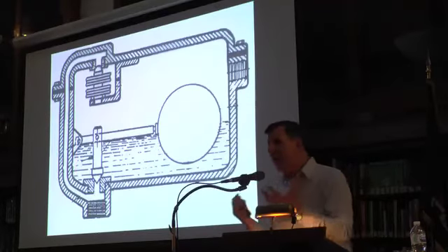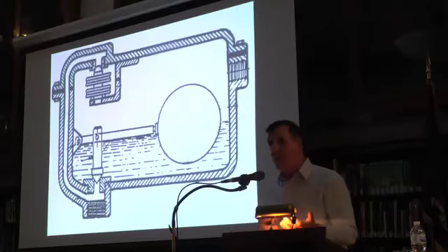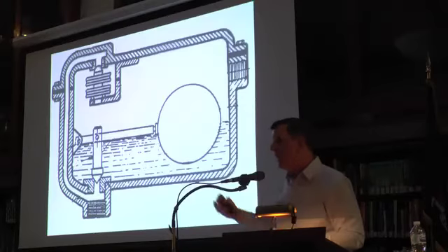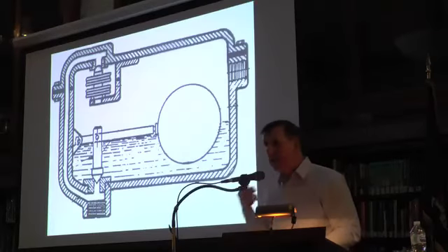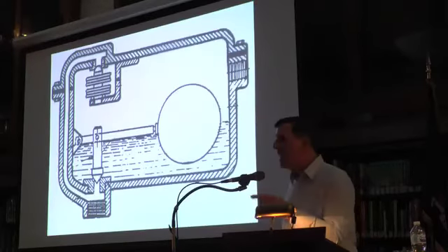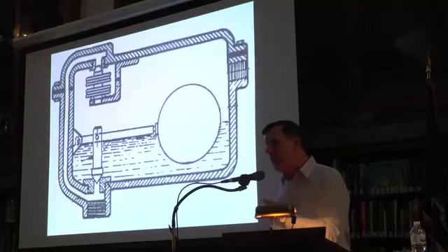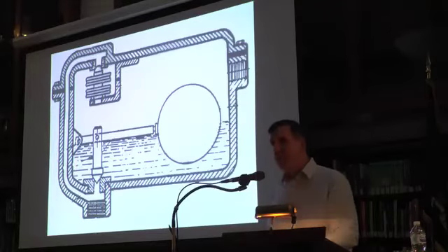So if you don't know how to size steam traps, get together with a steam trap rep, or go on a website like heatinghelp.com and read and find out how to do it. It's not complicated. If I'm able to do it, anybody could do it. And you size it properly. But I can tell you this with 100% certainty. If you're dealing with heating and you see a float thermostatic trap that's the same size as the pipe, it is the wrong trap in every single case. You paid more than you should have, and the thing's going to fail.